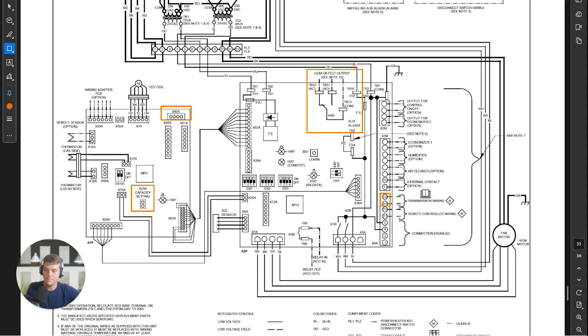So when we talk about that, you have to remember that this board is not sized to handle that load either. And so we should always be breaking something or a control source with a relay or some kind of isolation relay that can handle that actual draw of current that we're breaking. Again, I'm a fan of breaking neutral wires, common wires, just to avoid that. But, to each their own. Just know that you're not going to be using this main control board as your source if your current is, well, let's be honest, anything above 0. Now, it does do a little bit of things, but just remember that always needs to come to the forefront of your mind. So that's it.